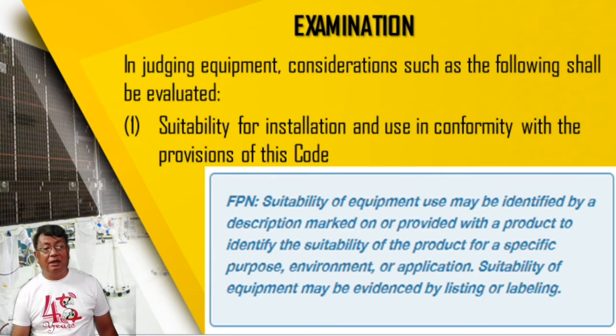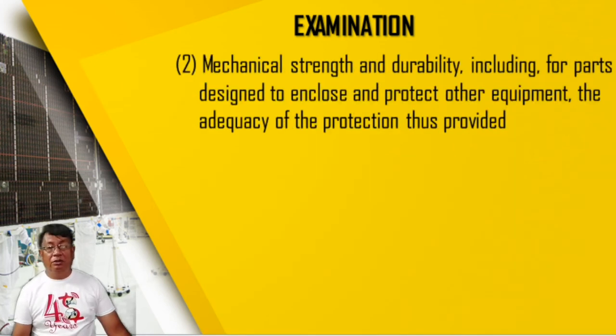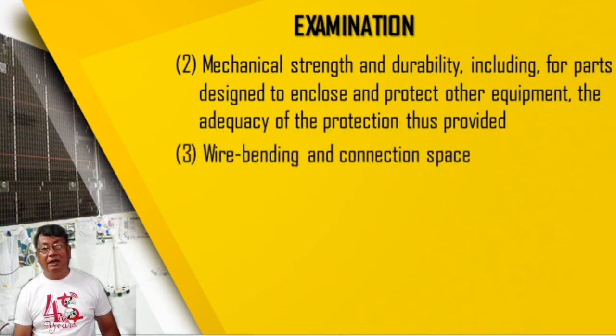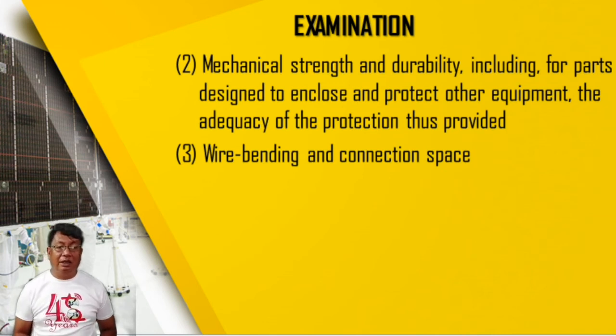Okay, so we have that FPN. So number 2 for the examination, mechanical strength and durability. Mechanical strength and durability for parts designed to enclose and protect other equipment. The adequacy of the protection thus provided. Okay, wire bending and connection space.